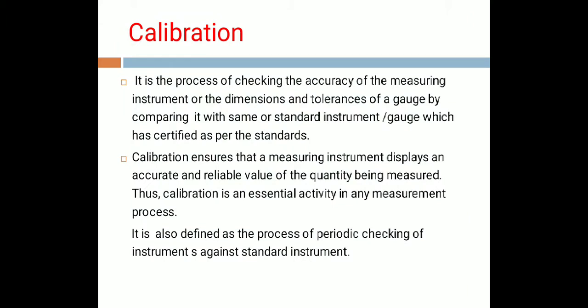The next topic is calibration. It is the process of checking the accuracy of a measuring instrument, or the dimensions and tolerances of a gauge, by comparing it with a standard instrument or gauge which has been certified as per standards. Calibration ensures that a measuring instrument displays an accurate and reliable value of the quantity being measured. Thus, calibration is an essential activity in any measurement process. It is also defined as the process of periodic checking of instruments against a standard instrument. That means when we are calibrating the instrument, we are always comparing it with the standard measurement instrument.